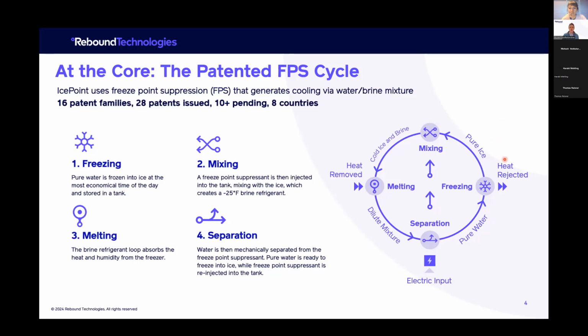If you map it to a temperature-entropy diagram, it looks just like a vapor compression cycle or any other heat pump cycle. I'll walk you through the states and steps. First you take your pure refrigerant — in our case, water — and freeze it. That's analogous to the condensing step of a vapor compression cycle, so it rejects heat to ambient, or in our case to our top cycle, which then rejects it to ambient.